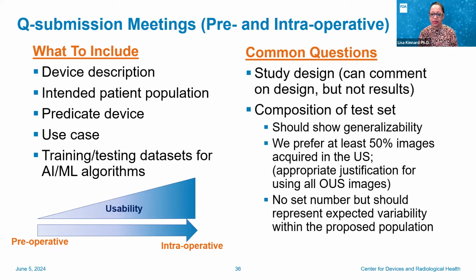Other questions that come up are about the composition of the test set. Your test set needs to show that it's generalizable to other populations, other imaging acquisition parameters, and other image acquisition devices. We prefer to have 50% of the images acquired in the U.S. That's not a hard and fast rule, but it's a preference. If none of your images are acquired in the U.S., we need to know, and we need an appropriate justification for using all images outside the U.S. Another common question is how many images are needed. There's really no set number. We just need to see that the numbers reflect the expected variability within the proposed population.